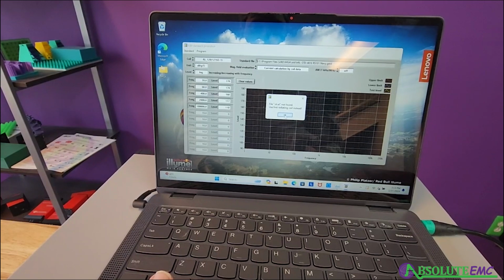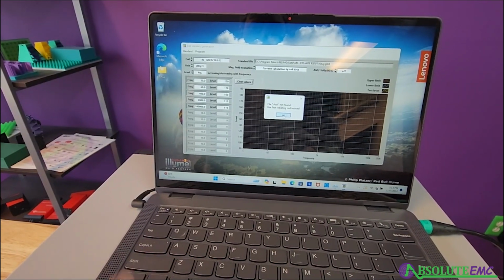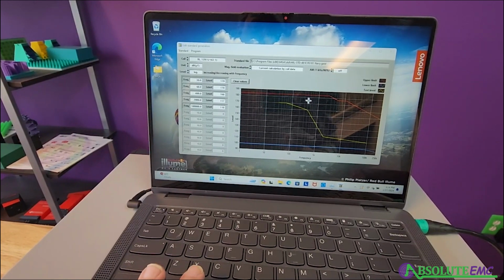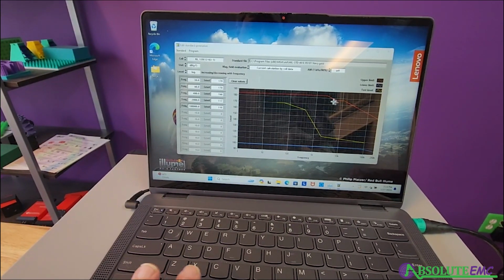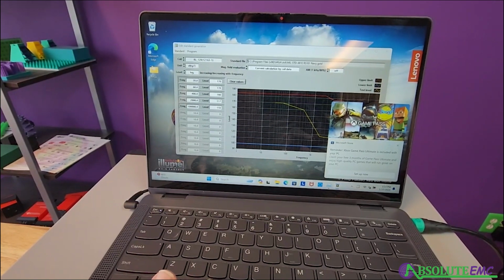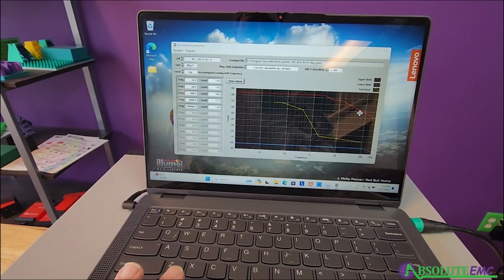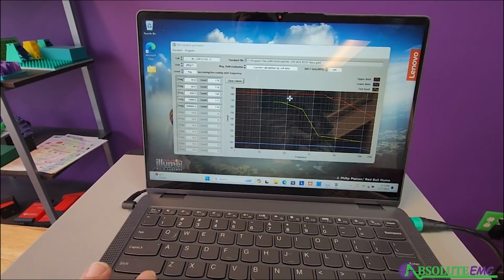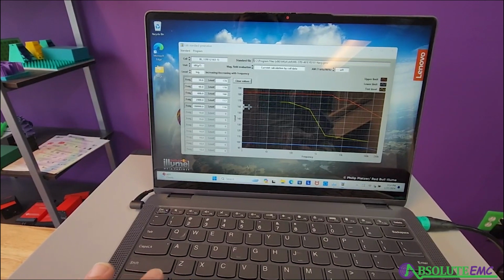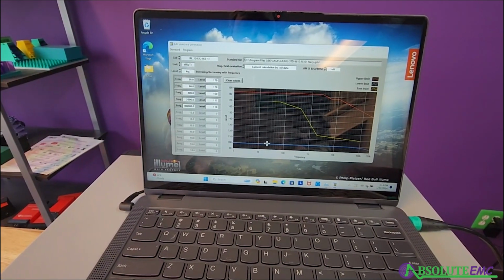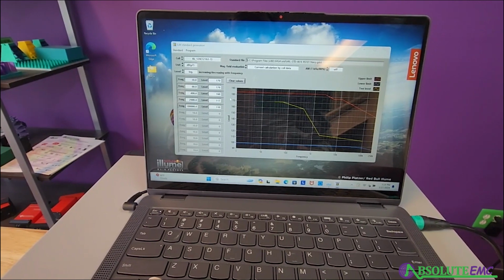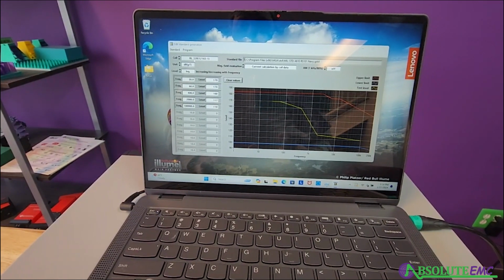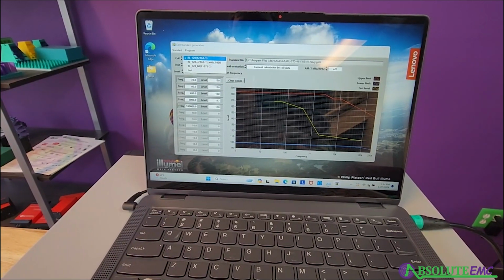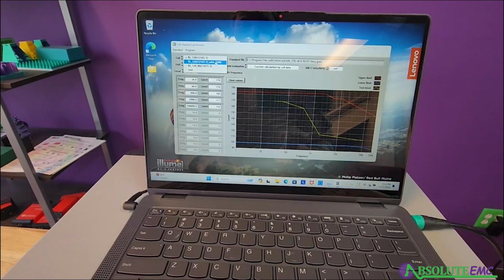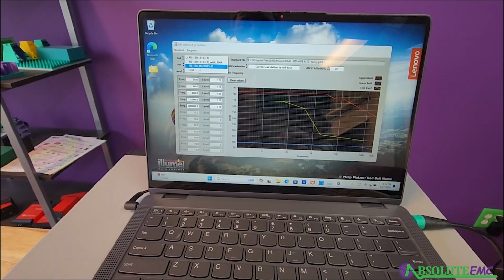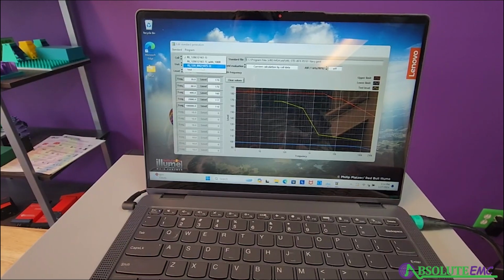So it's saying it needs a cal file, just means that we haven't run any tests yet. Okay. So we have here, the red line shows our maximum available level. Oh, there's Windows jumping in there. That we can put out. The yellow line is the standard that's defined over on the left here. And then the blue line is our minimum field we can generate. Right now we have the coil set for the RL120, that's what's hooked up. We have the RL120 with the resistor, and we also have the low frequency RL120-80 in here.